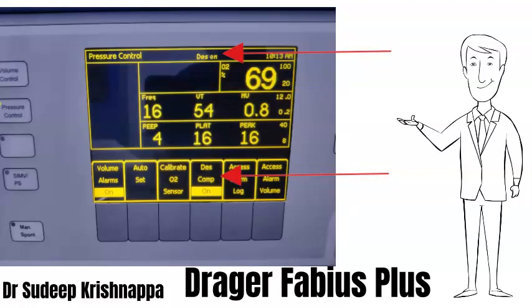Whenever these machines are using desflurane, they have an option of switching on desflurane compensation, which can be chosen from the menu as indicated by the lower arrow. When you switch on desflurane compensation, a symbol at the top of the screen indicates that desflurane compensation is indeed switched on.